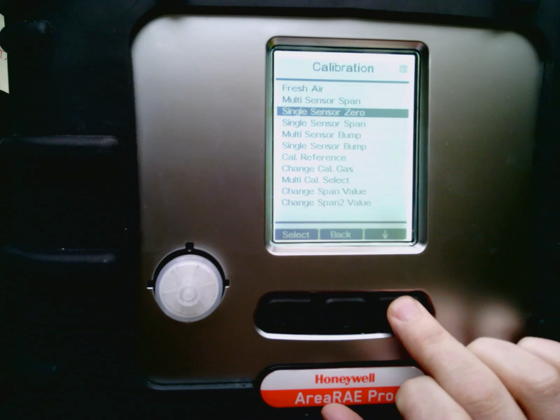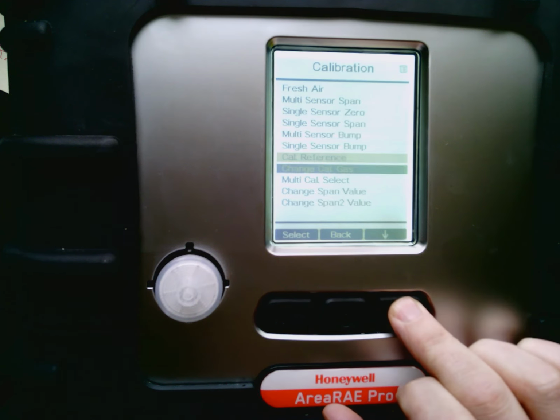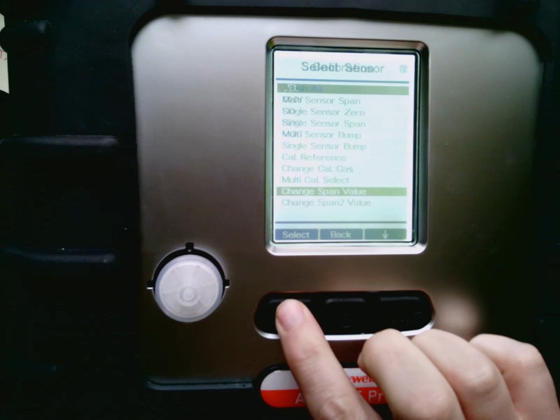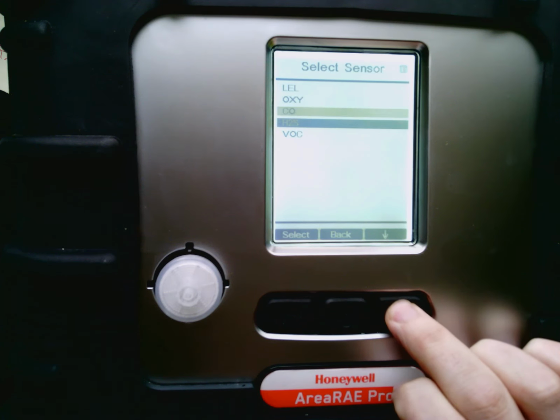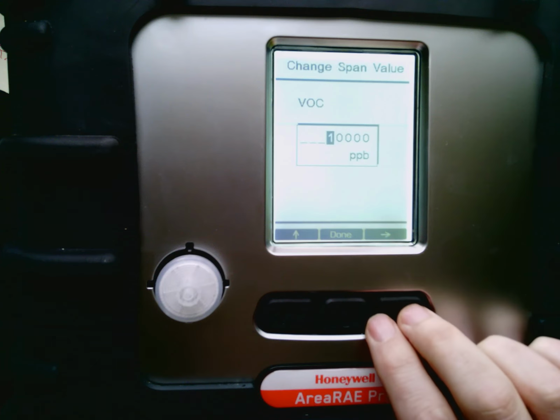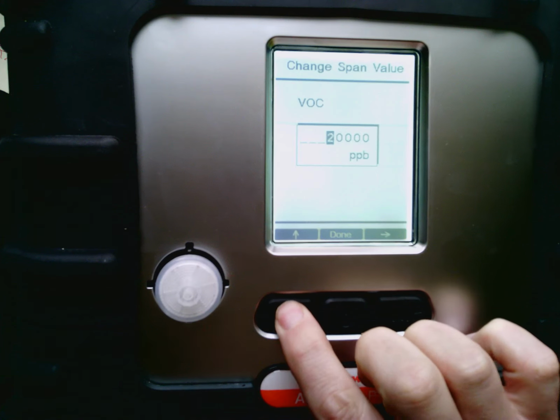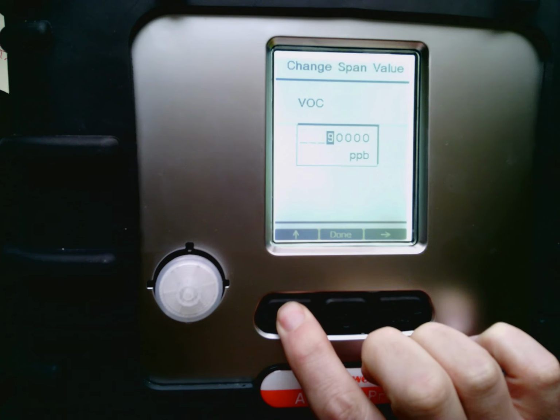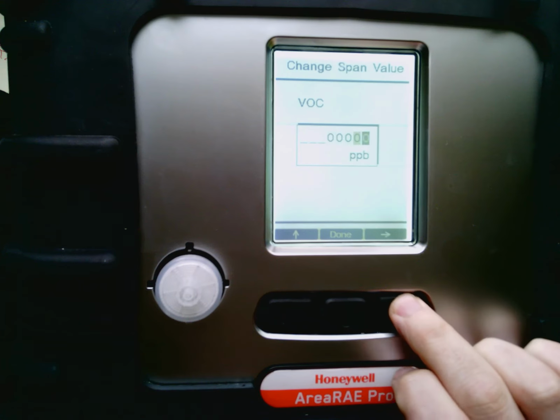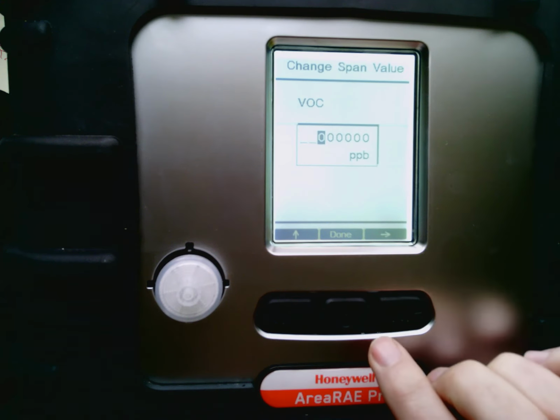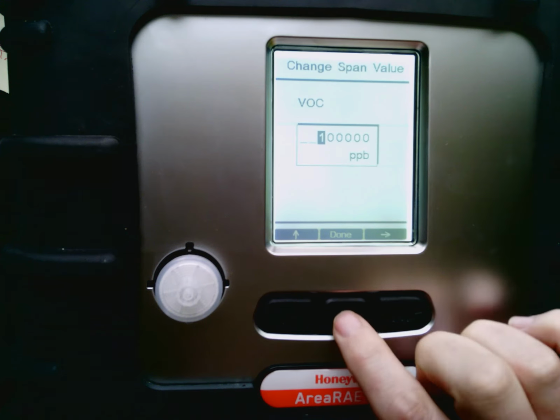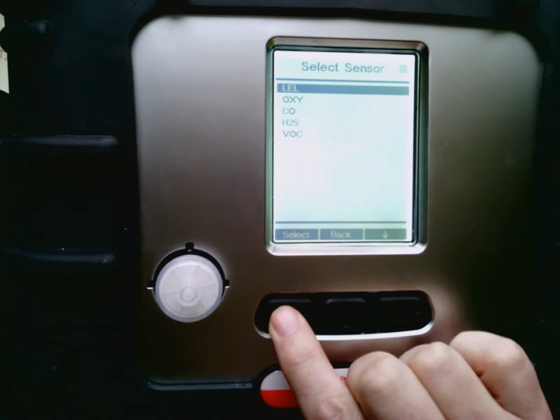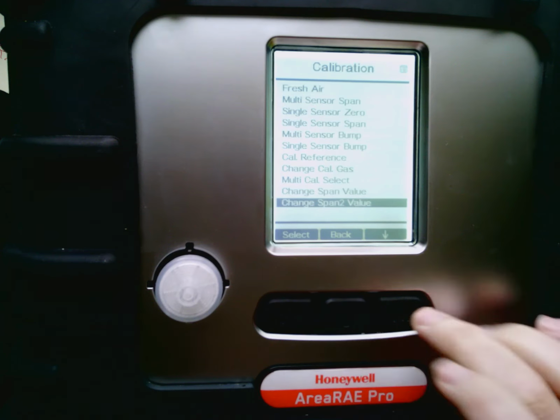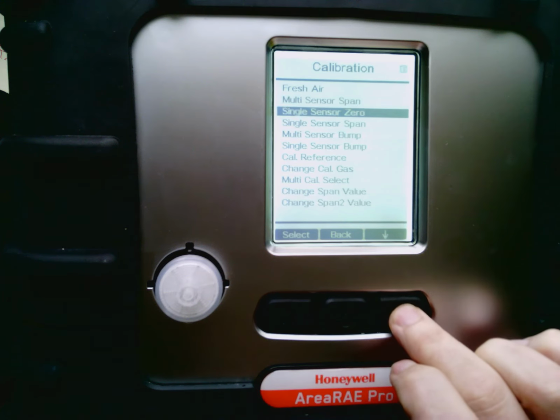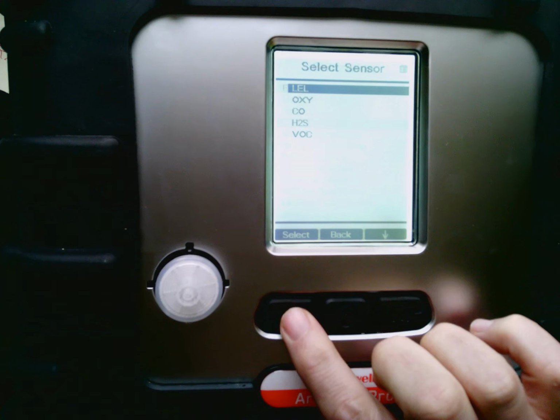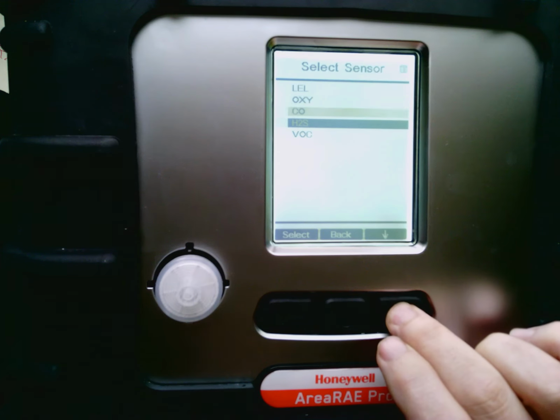To change that, again using the soft keys, I'm going to mode down to change span value. I'm going to hit the select button, and I'm going to mode down to the VOC. I'm going to hit select, and I'm going to change this to a 0 and add 1 to it. 0, and let's get over to this one here and add 1. Whoops, 1. And I'm going to hit done, and I've got to save it, and go back to the menu and go to single sensor span, and I'm going to hit select and scroll down to where it says VOC.